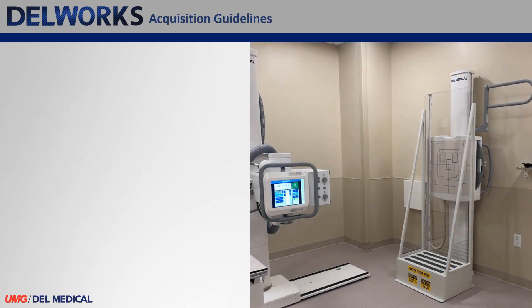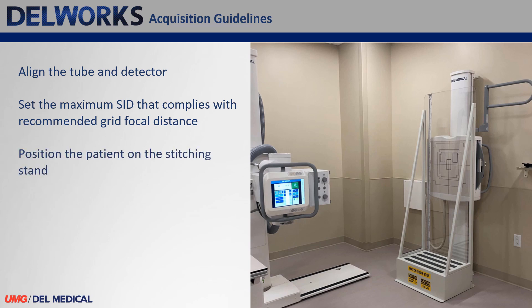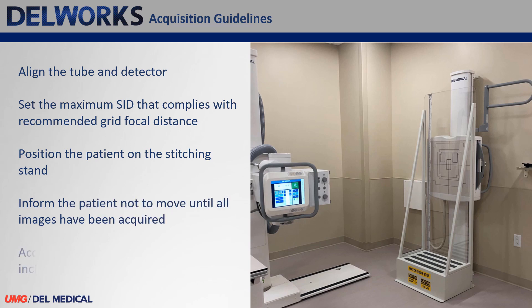First, it is important to prepare the room for your stitching exam. Align the tube and the detector, set the maximum SID that complies with the recommended grid focal distance, position the patient on the stitching stand, inform the patient not to move until all images have been acquired, and acquire images with a minimum of 2 inches of overlap between each image.